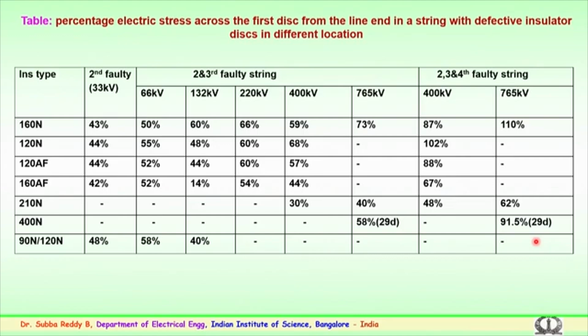So, this is a very important study which has been done. It gives very important information: in case the insulator units are faulted after the middle of the insulator string, not much of a worry, whereas if the discs are faulted near the line end, after the first insulator, the second, third, fourth, it is very serious, and the utilities have to immediately take necessary action in changing the insulator and bringing down the stress level across the first disc insulators.